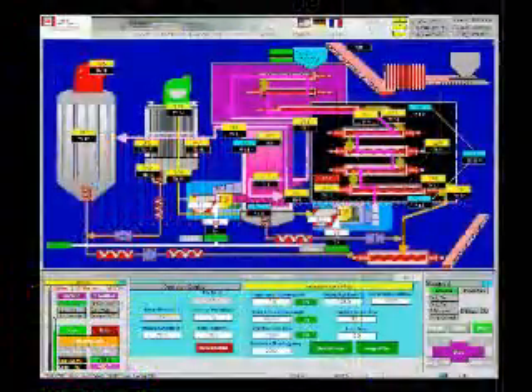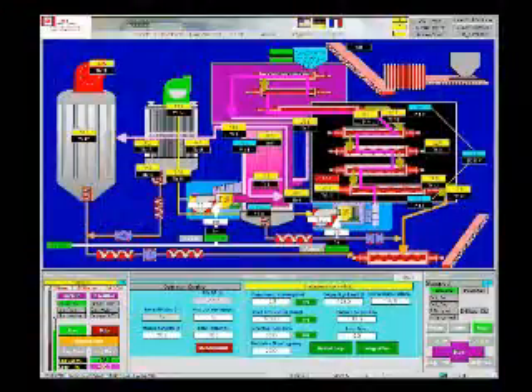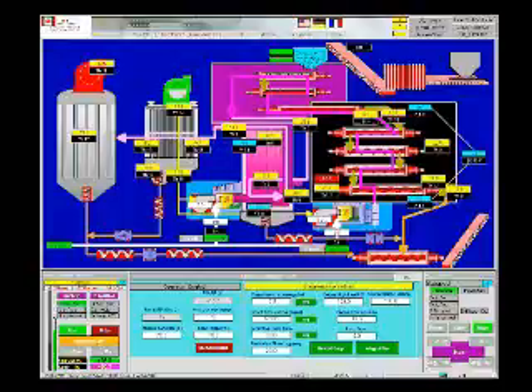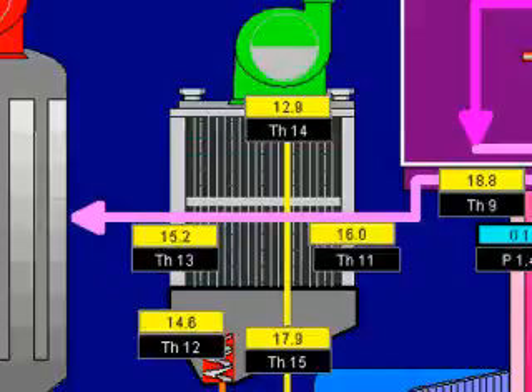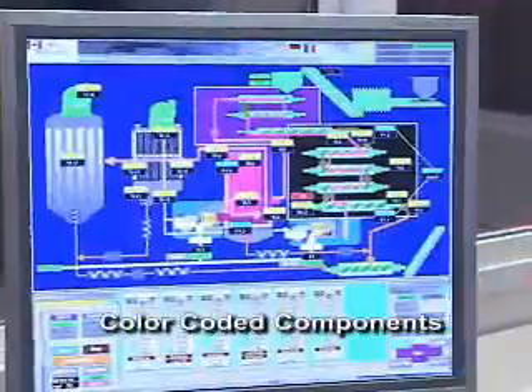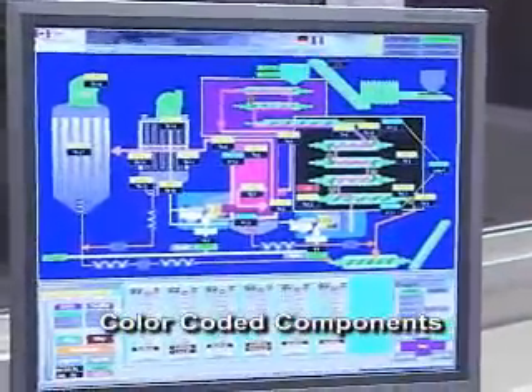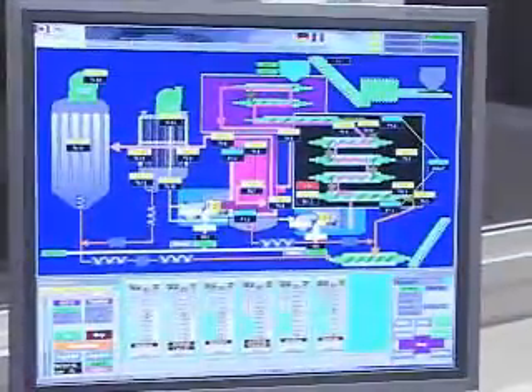Here you will see the hopper. Then there are the screw conveyors, thermal oxidizer, processor, sensors, and so on. Each image is complete with all the relevant production data for that component. For example, the heat exchanger shows the air temperatures to the baghouse and to the burners. The color-coded components on screen give the operator the ability to monitor all systems simultaneously.